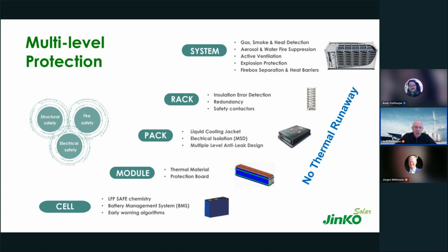But a large proportion of the fires is caused by nothing to do with the battery itself, nothing to do with the cells. It's to do with the leakage of liquid onto the bus bars. Okay, so something as simple as a fault that causes a leak. Water and electricity don't mix very well. They don't make very good partners. So the system is really designed that it will detect leaks. We don't have to do that in terms of the certifications, but it's something that we see as being necessary to do to give extra assurance and extra comfort to the user.